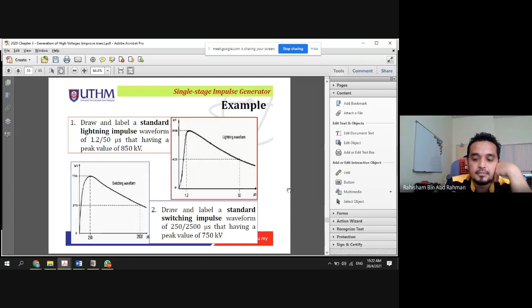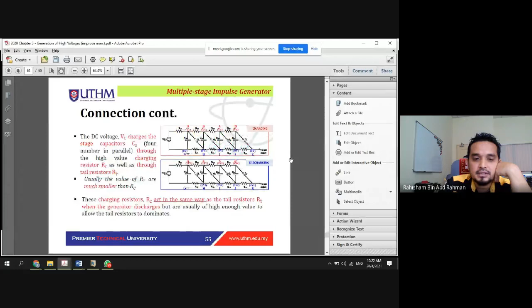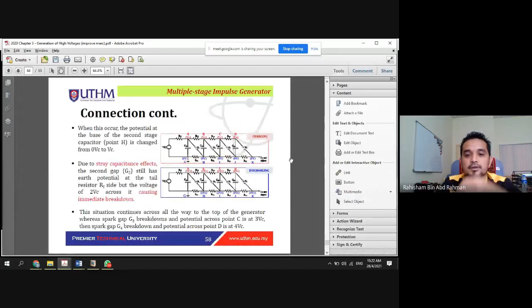So we might end up with a 400 kV impulse generator. That is the arrangement of this equipment for charging and discharging of this multiple stage impulse generator, and we have the test object here. If we can see, initially the voltage is 0 and this one is VC. Once we trigger it, this becomes 1VC, then this one 2, this one 3, and this one 4 - 4VC to the test object.